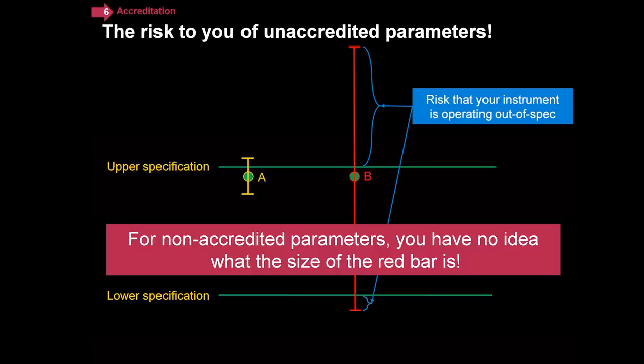You might ask: does this really happen? Let me make this real. I was just in the Bethlehem lab and saw three brand new digital spectrum analyzers — when you look at any of our microwave receivers and go down to minus 100 dB, you're off by less than 0.06 dB. It's amazing. But if you were to use any of our 1980s or 1990s spectrum analyzers without digital IFs, the uncertainty would be much wider. So it matters. In my experience, when a lab offers calibration where they're not accredited, they're often using older instruments. No auditor would allow large uncertainties like that — you just wouldn't pass the audit. That's another way you have assurance we're using instruments with the proper uncertainty and accuracy.